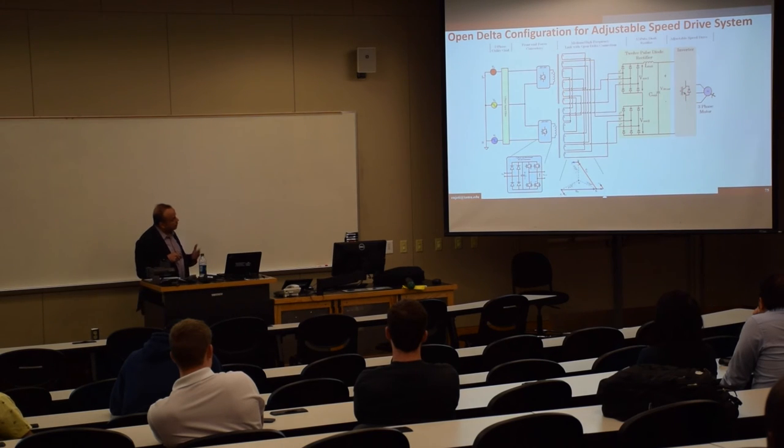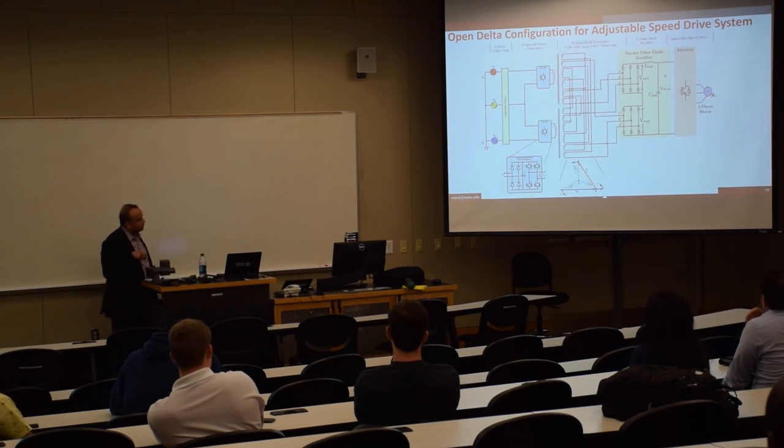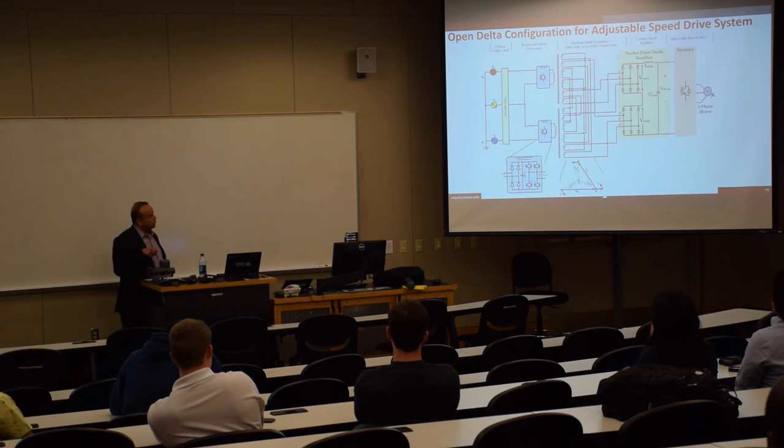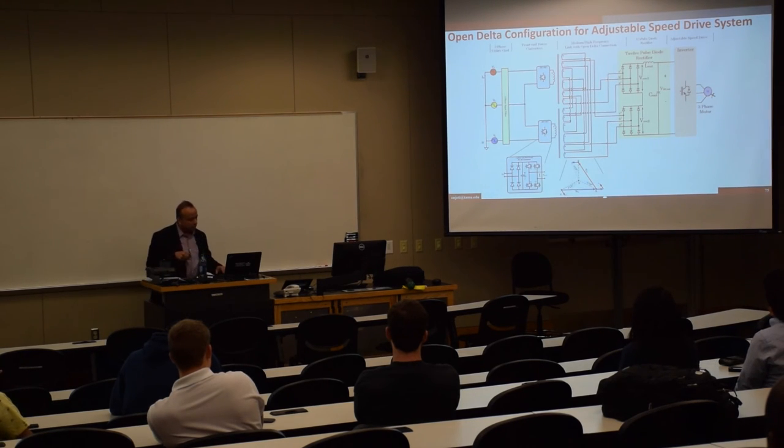And the same concept, if you want to do open delta, means you take two single-phase medium frequency transformers and shift them. One creates a minus 15 this way, and the other transformer creates the plus 15 that way, and then you just use a 12 pulse for the drives.